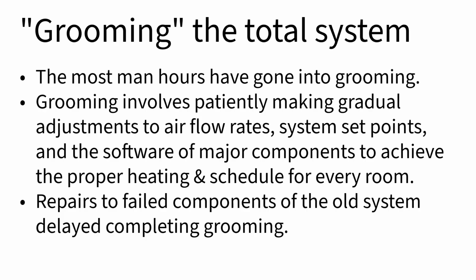Most of the time from January through March goes into what we call grooming. That means we have to very patiently make gradual adjustments to the airflow rates through the heating ducts coming down from the air handling units on the roof, to the system set points, the temperatures at which various components trigger on and off, as well as the set points for all the individual rooms depending on how they're used, and the schedule for the use of those rooms.